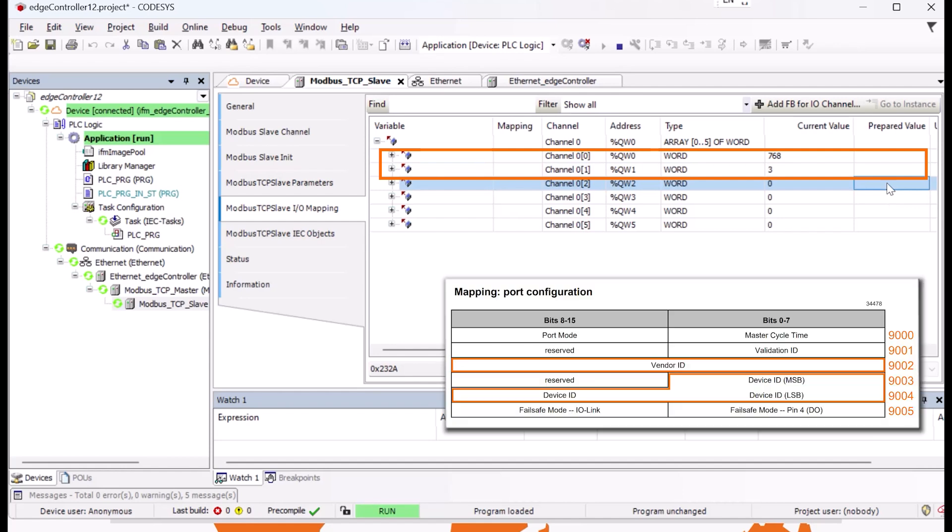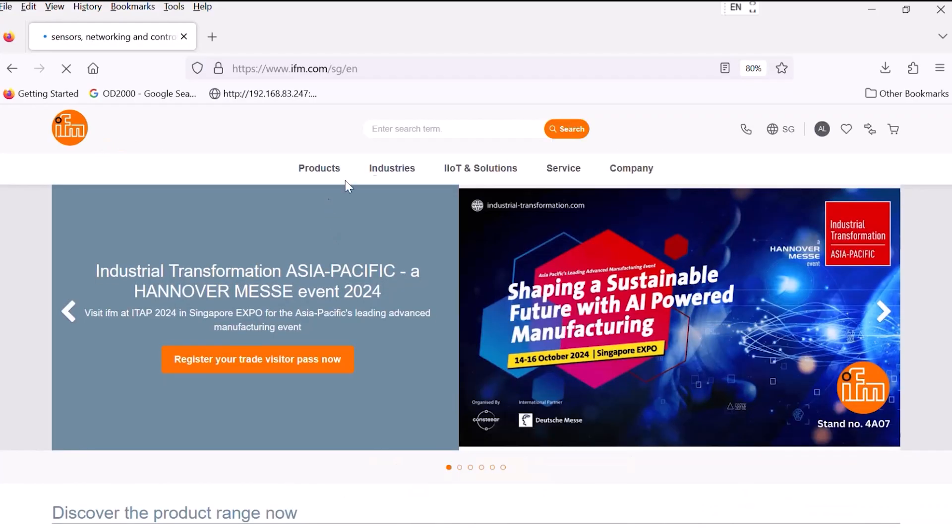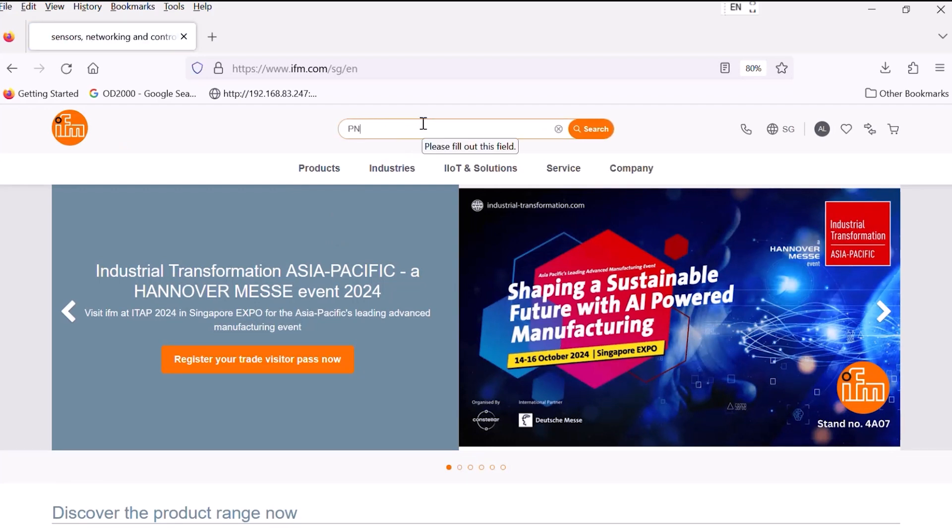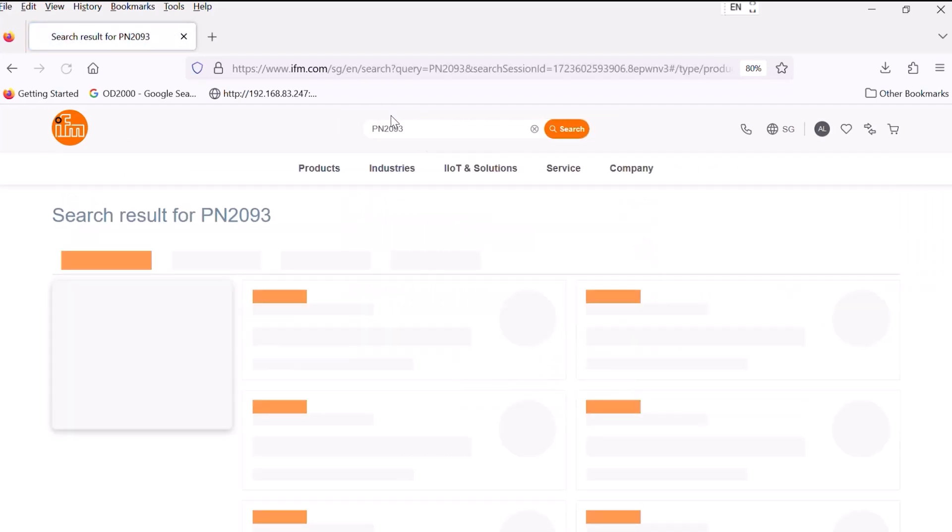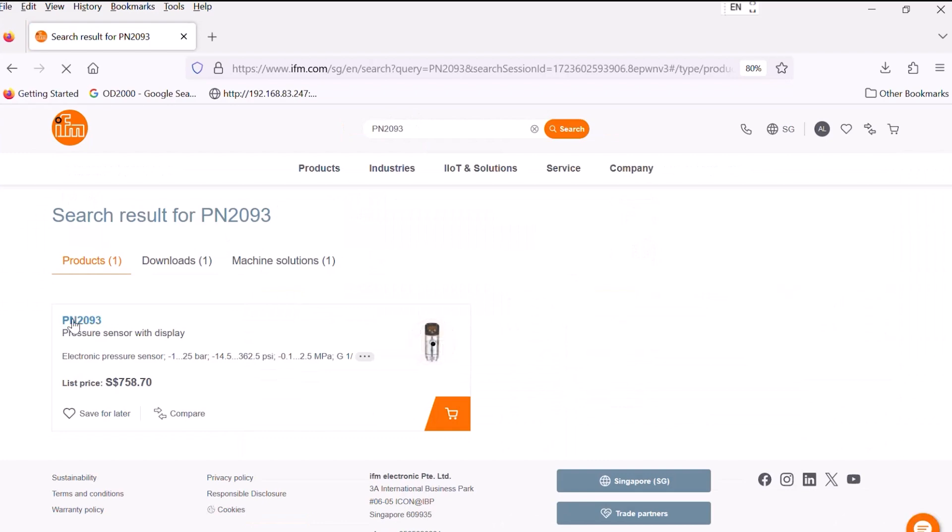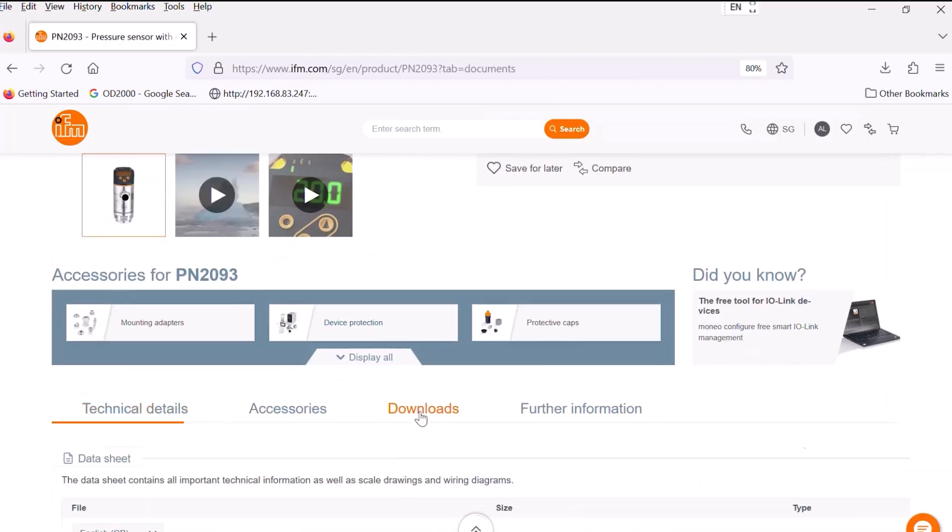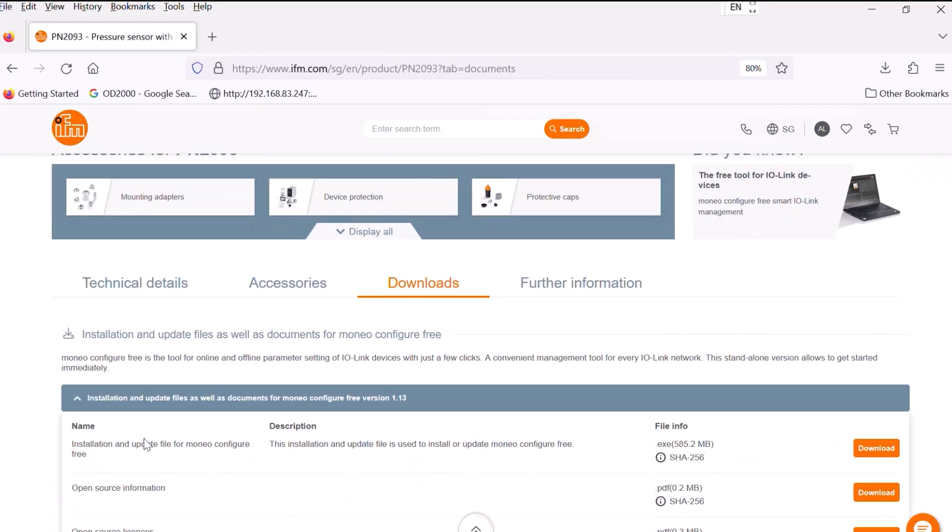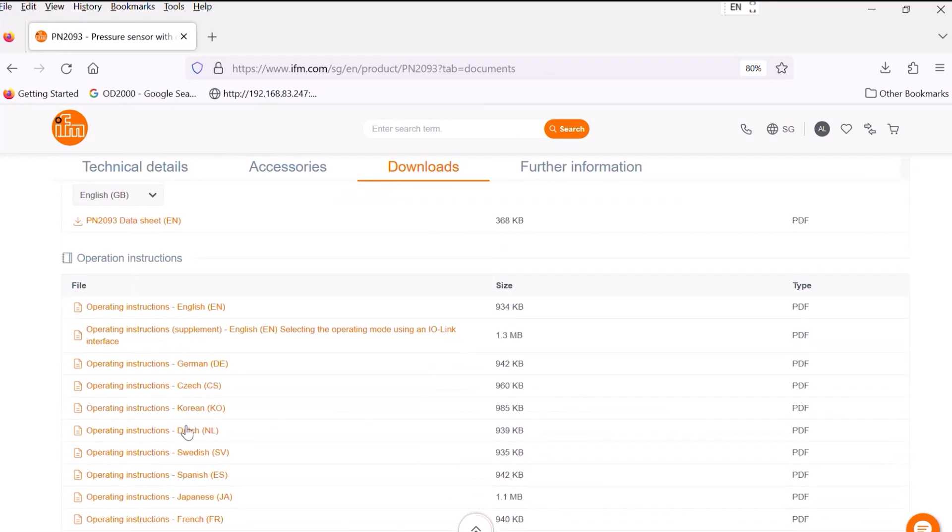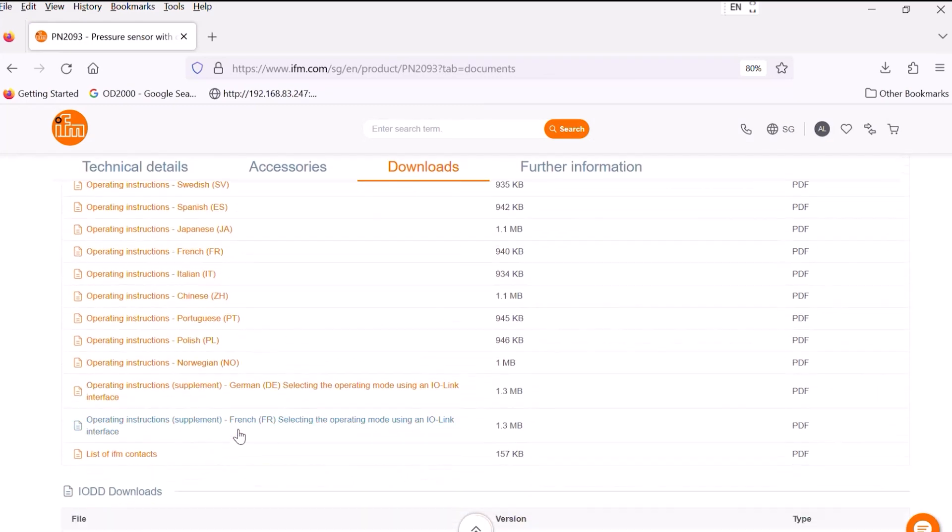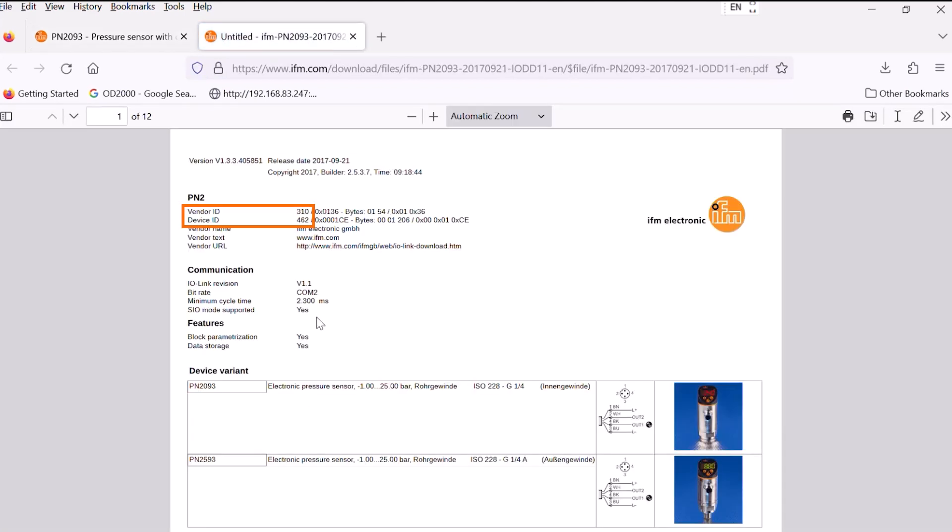Finally, we need to change the vendor and device ID for port 1. These information can be found in the IODD PDF of the PN2093 pressure sensor we use. On the IFM homepage, the search function takes us directly to the online datasheet for the sensor. In the Downloads area, we scroll down and select the IODD PDF. On the first page, you will find the vendor ID 310 for IFM and the device ID 462 for the PN2093 pressure sensor.